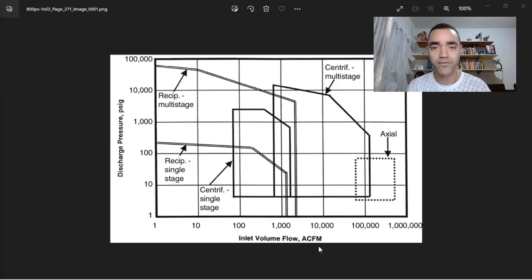So when we have a compressor or a rotating equipment that is identified as actual cubic feet per minute, it means that the process conditions for pressure and temperature are your operating conditions. If it is 40 Fahrenheit or 15 PSIG, it will be the conditions for the actual volume flow. And it's important because when you do the conversion to normal cubic meters or standard cubic meters, the values can be very, very different. So this is the first point.